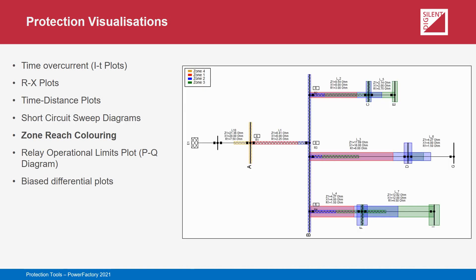Zone reach coloring is another distance protection-specific visualization. In this case, the visualization is shown directly in the single line diagram instead of in a specific plot. The theoretical reach of selected distance device zone settings can be overlaid on the single line diagram based on a comparison of the zone settings to the impedance of the protected lines. Configurable coloring and shading is used to aid differentiation between zones. Zone reach coloring is also initiated using the Protection Graphic Assistant tool.